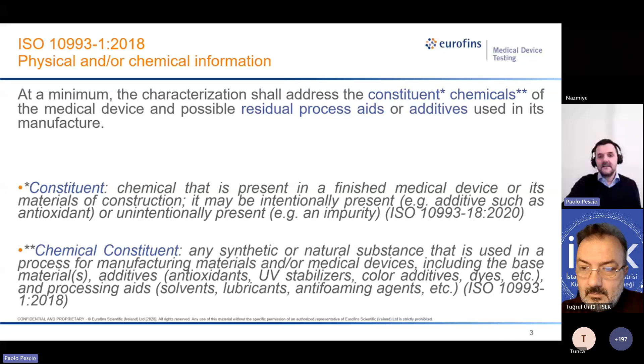But I say that we have three definitions because in September last year we have this new definition coming from 10993-17. A chemical says that a constituent is a chemical that is present in or on the finished medical device or its material of construction. So there is this specification that the chemical can be present also on the surface of the medical device, and the rest is the same as in part 18. So something that can be intentionally or unintentionally added to the medical device. So the definition of part 18 was modified to make clear that a constituent can be also on the device.